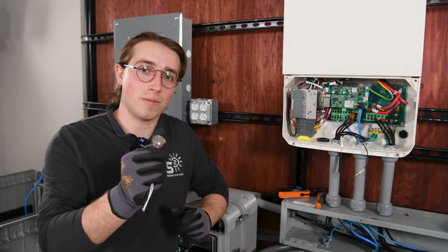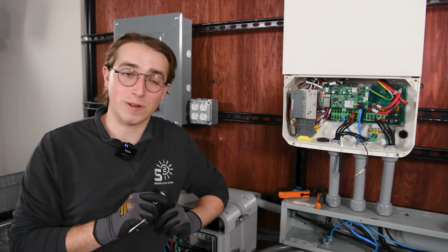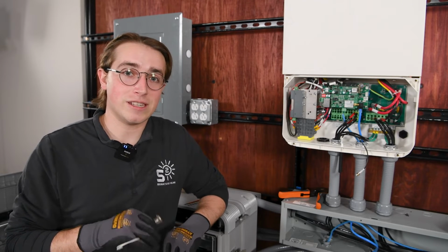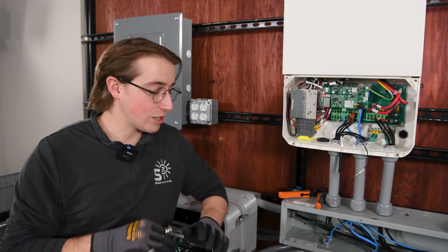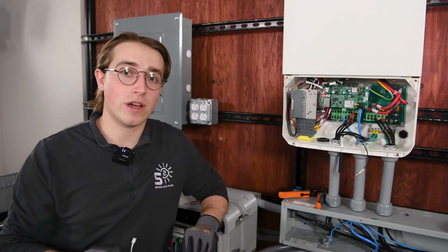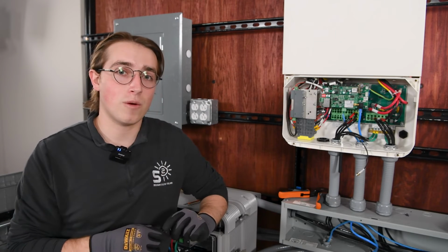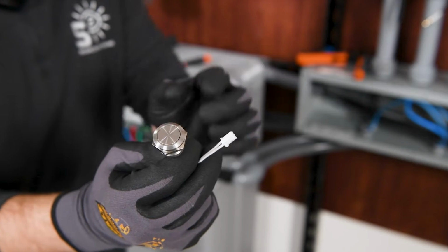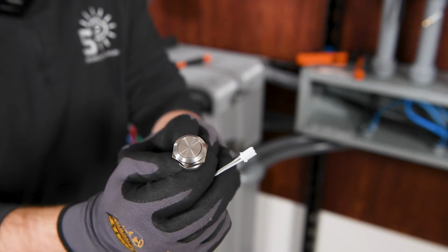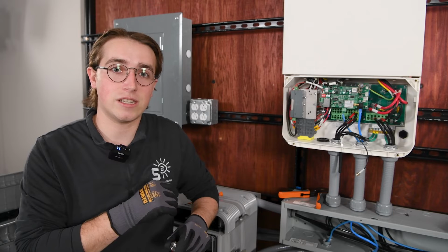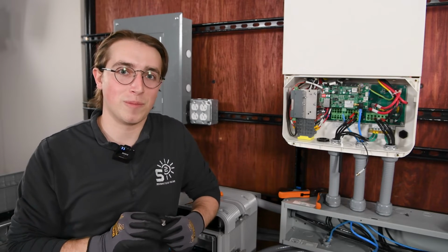Here is their Darkstart button, which I will show you how to wire up shortly. The Darkstart feature is essential for multi-day grid outages, especially when the batteries are depleted throughout the day and the inverter's having a hard time waking up in the morning. All you have to do is click the button, which is going to enable the inverter to start using the PV power that it sees in the morning to charge the batteries when they're completely dead.